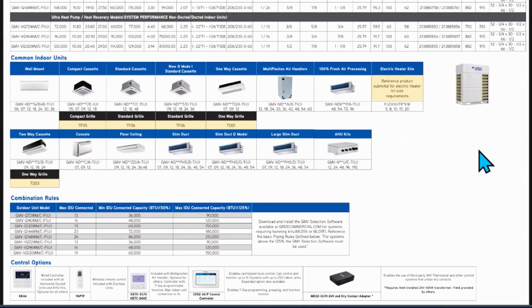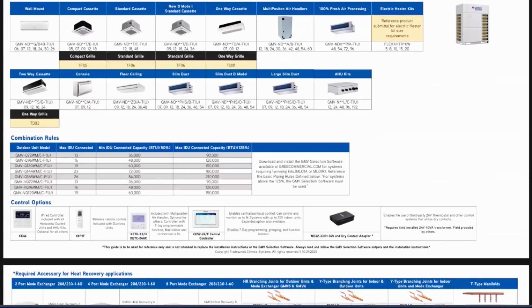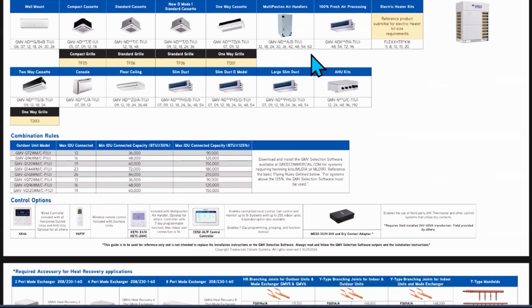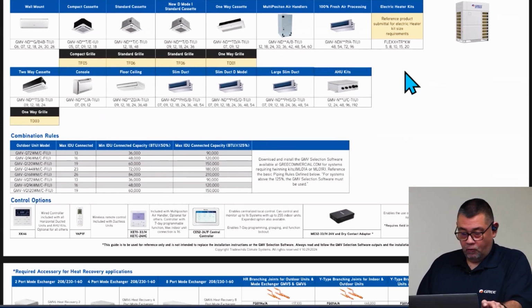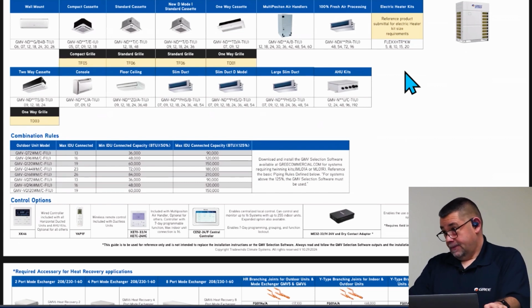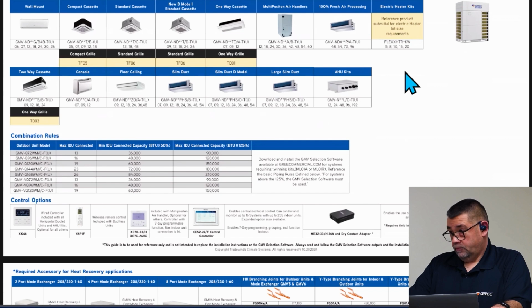Yep. The other thing that we want to talk about here and highlight is the combination rules. So on our 6-ton, the maximum number of indoor units you can connect is up to 13. And the minimum capacity connected is 36,000 BTUs, or 50% of the rated capacity of the outdoor unit. I've talked about that many times with single-phase MultiPRO. Your connection ratio is 50 to 125%.